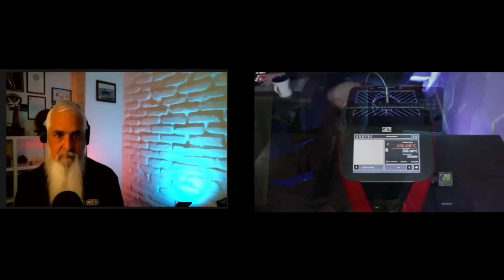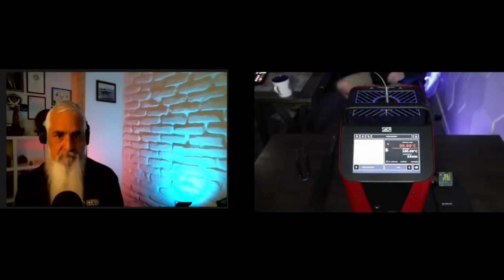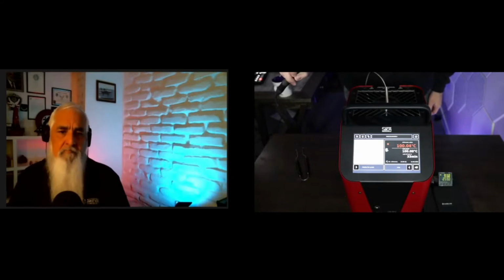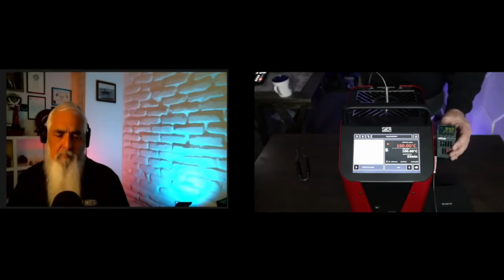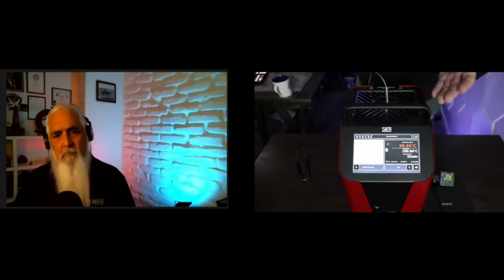So it looks like it's sitting at close to 100. Right now we're at right around 100.04. But notice, everybody, how even though our thermocouple is a fast-reacting temperature sensor, it's taking a minute because it's in a probe, and the entire well needs to come up to a stable temperature before we're expecting to see a perfect reading here.